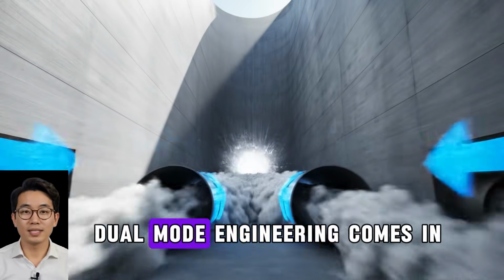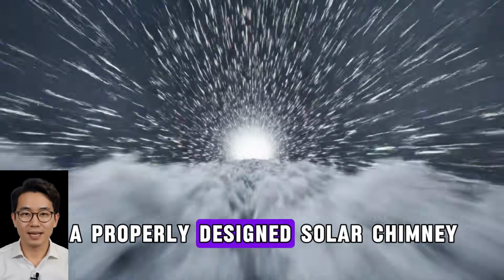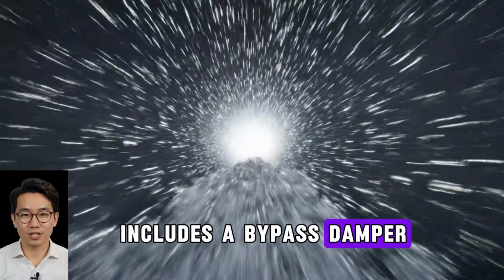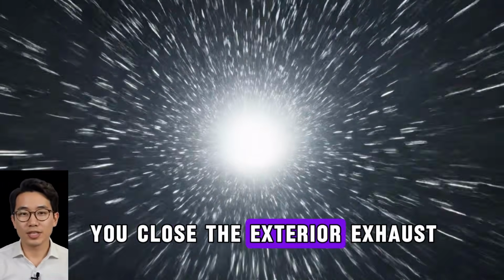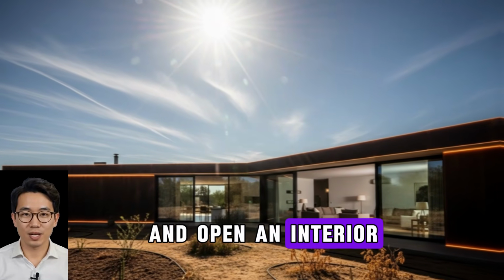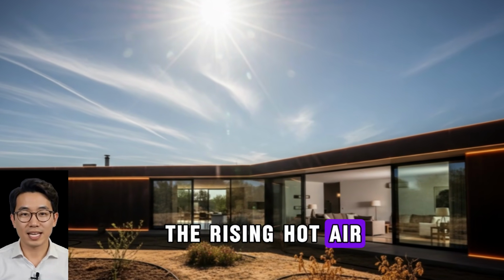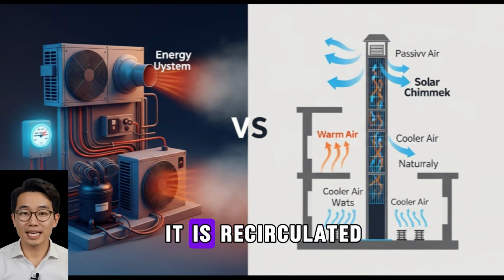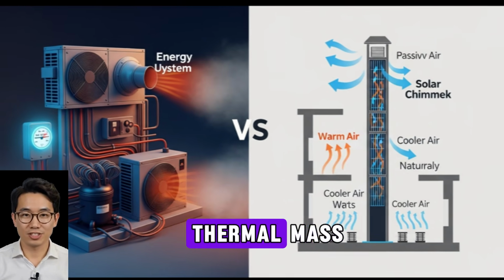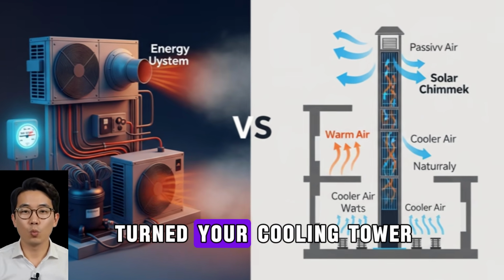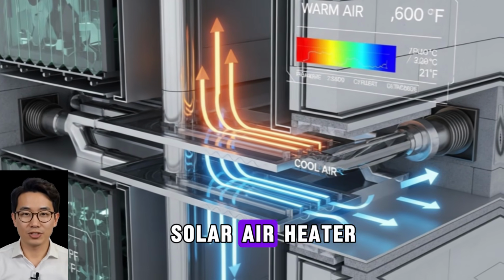This is where the dual-mode engineering comes in. A properly designed solar chimney includes a bypass damper. In the winter, you close the exterior exhaust and open an interior return vent. The rising hot air is no longer dumped outside. It is recirculated back into the building's thermal mass. This effectively turns your cooling tower into a massive solar air heater.